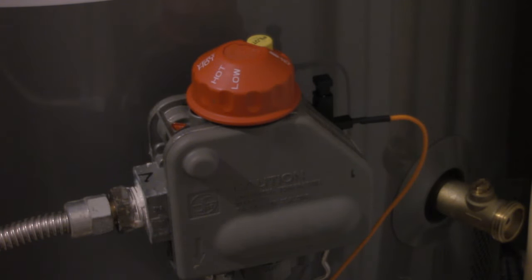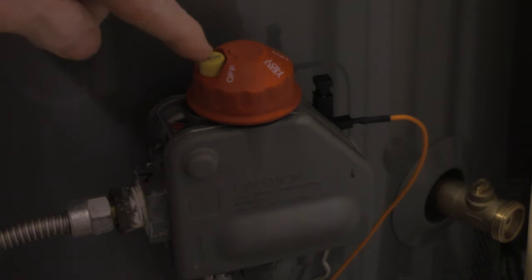Okay, so now you've got everything open and you can get to it, go ahead and turn your gas valve all the way over to pilot. You know you're in pilot when you can push the pilot button down. If it's set anywhere else, you cannot push that little yellow button down or whatever color it is on yours.